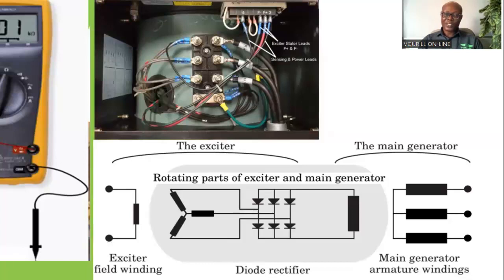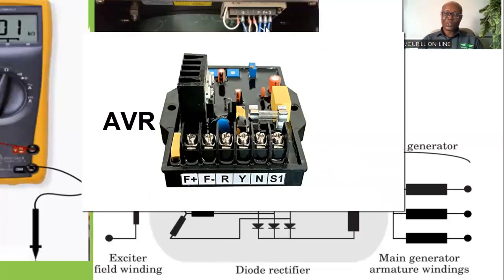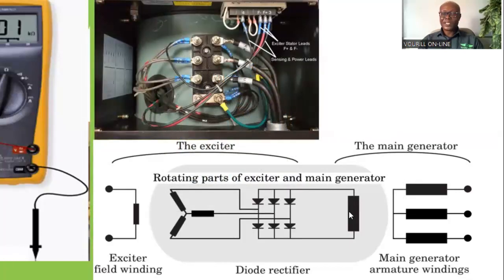So these are the 2 wires that go to the AVR, and the AVR supplies the exciter field with DC voltage that helps create the magnetism that induces voltage into the exciter armature. The voltage induced into the exciter armature is rectified and sent to the main field, which will in turn magnetize the main field, and that rotating magnetism, since the rotor rotates when the generator is working, will induce voltage into the main armature, where you get your output power from.